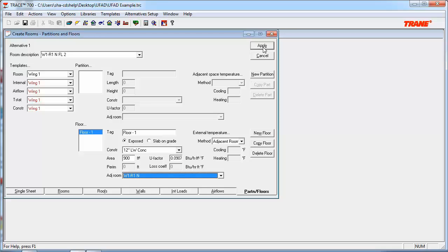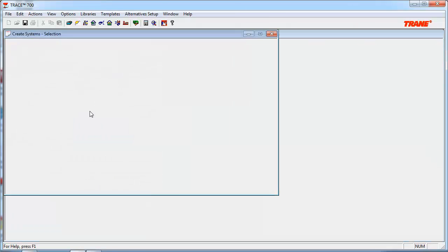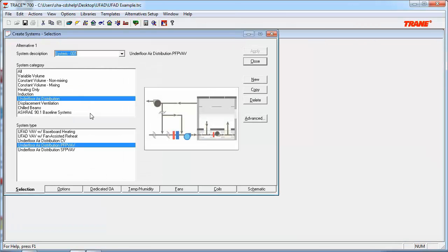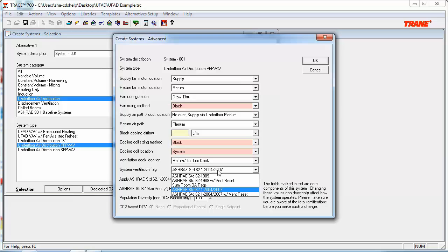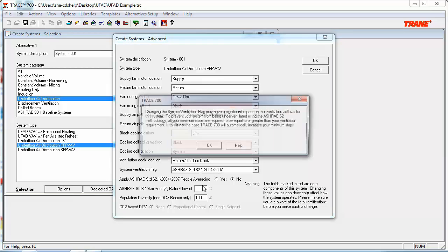So, once we have completed all of our inputting the floors, which I've already done in advance, we can now focus on the systems. We can go ahead and select the proper UFAD system type, which is already done, from the list in the Selection tab. So, I've already chosen Underfloor Air Distribution Parallel Fan Power VAV System Type. Then we need to click on the Advanced button, and we need to turn on the ASHRAE 62.1-2007 calculation for the system, so we can run the ventilation calculation at the system level. So, in this case, for this input, make sure you're selecting Standard 62.1.